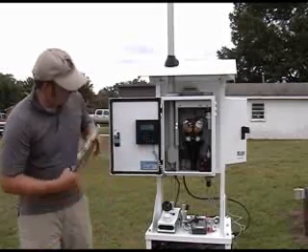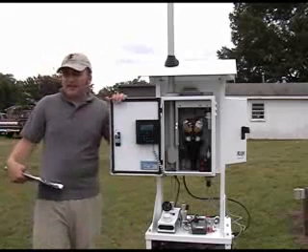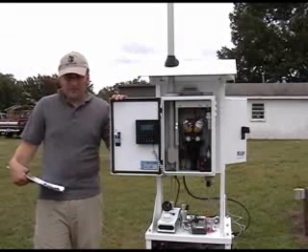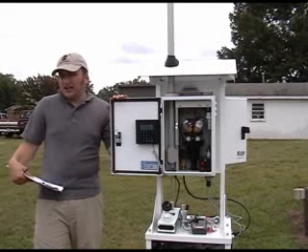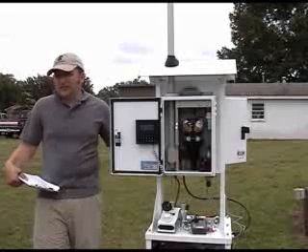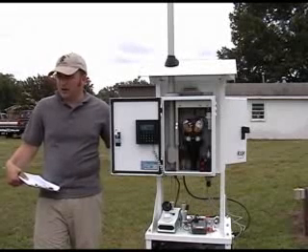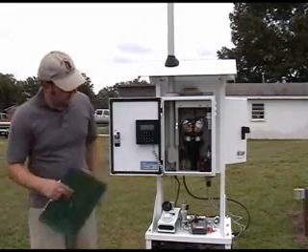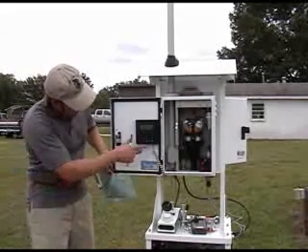Sampling interval. This is basically the interval that data is written to the data card. By default, it's 15 minutes. I don't know of any reason for changing that. I mentioned before that if your new data card is bad, you could leave the existing one in place because there's plenty of memory on the card, and I'm pretty sure that's what RTI will ask you to do if that arises. So no reason to change that.